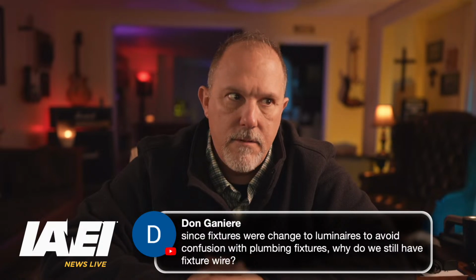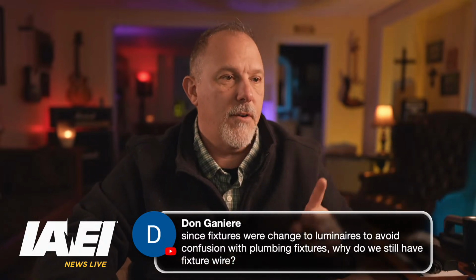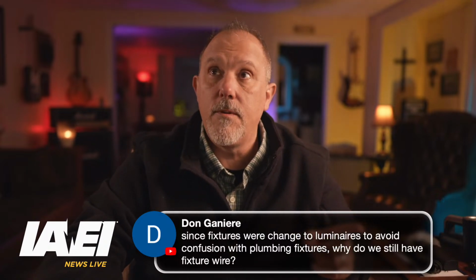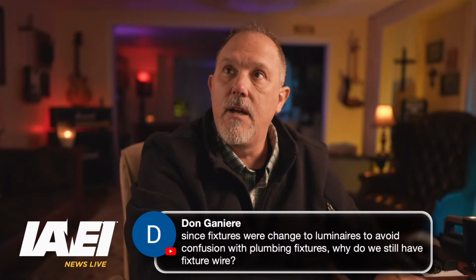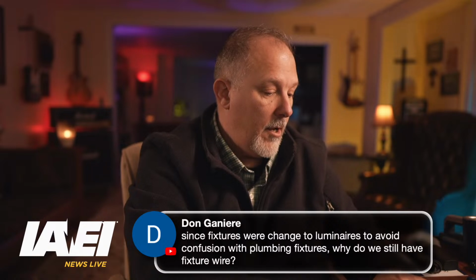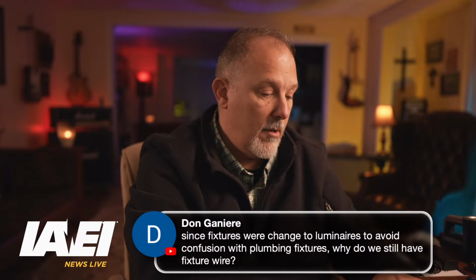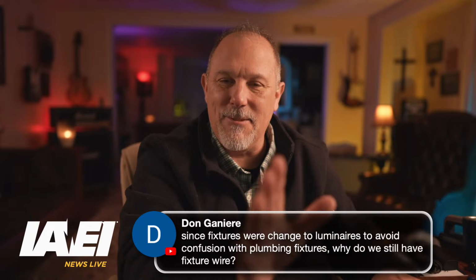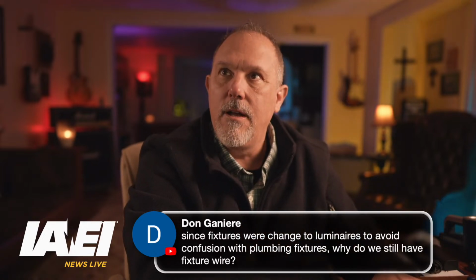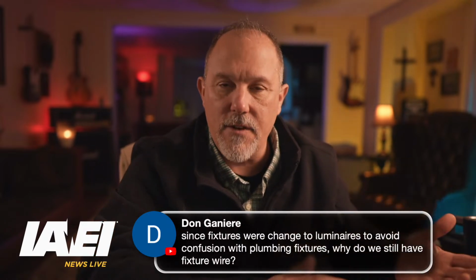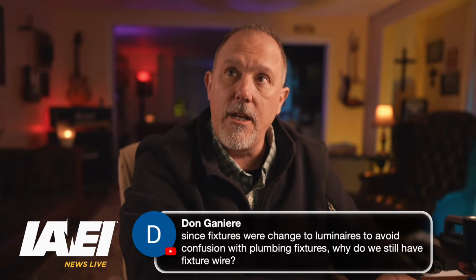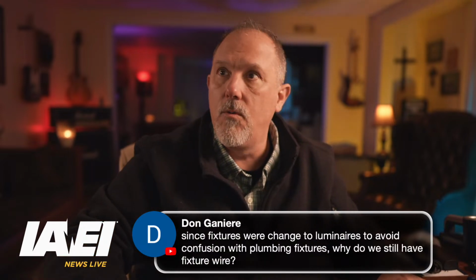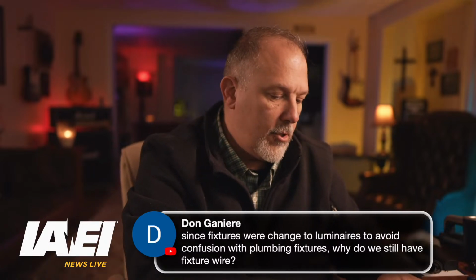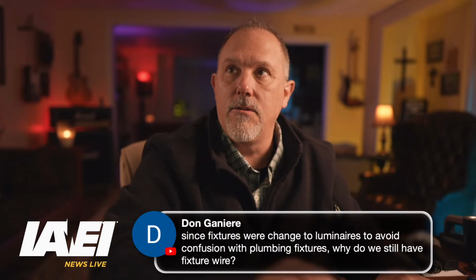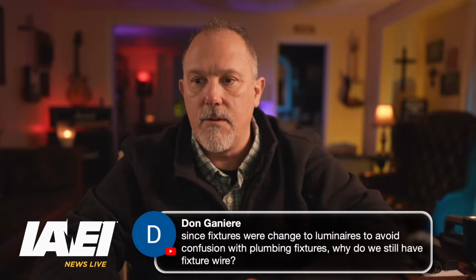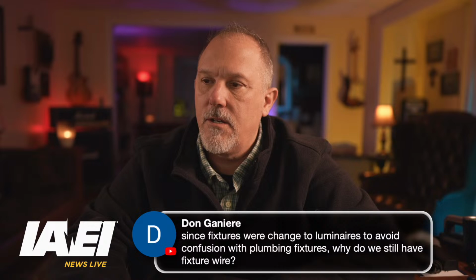I believe we may just have uncovered — I'm doing this now for NEC 2029 public inputs — number one, a defined term for fixture wire, not just 'fixture wire' used loosely. I think we also need a defined term for flexible cable, and a defined term for cable itself — we don't even have a definition of what a cable is. And then we need to change the title of Article 402 to luminaire wires instead of fixture wires. That's what I would do. Maybe that's a good public input, Dawn — here's what it'll do.